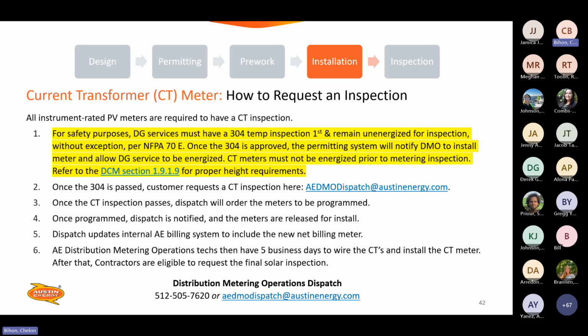All instrument-rated PV meters are required to have a CT inspection. For safety purposes, DG Services must have a 304 temp inspection first and remain unenergized for inspection without exception. This is per NFPA 70E safety. Once the 304 is approved, the permitting system will notify DMO to install the meter and allow DG service to be energized. CT meters must not be energized prior to metering inspection. Refer to DCM section 1.9.1.9 for proper height requirements.